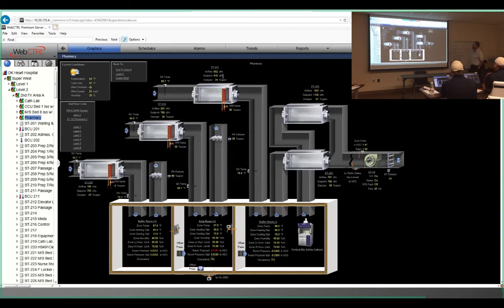This is another one of the different things. We're actually using VAV boxes to control. You noticed in your ORs you had dampers, just a Belimo actuator on a damper, using that to control the return into the space to control space pressure. These are actually return VAVs, with nothing in them other than the damper and the VAV controller.